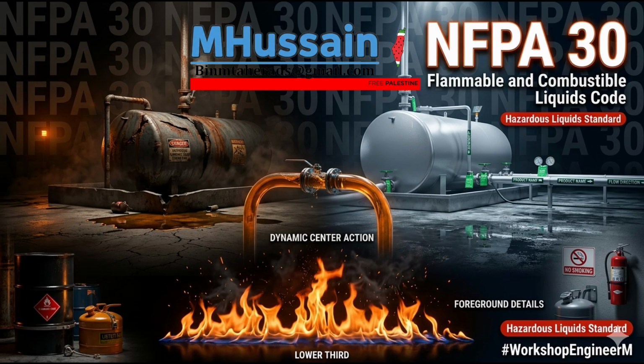Because the code is calculating radiant heat flux. If a 100,000-gallon tank of crude oil ignites, the thermal column generates a radiant heat footprint so intense it can easily ignite the roof of a building hundreds of feet away. Or cause a neighboring tank's steel shell to buckle. Exactly. The code mandates vast clear zones, so a single tank fire cannot geometrically bridge the gap to the rest of the facility. But the spacing isn't uniform. The code allows tighter grouping depending on the physical engineering of the tank itself, specifically differentiating between fixed roof tanks and floating roof tanks.